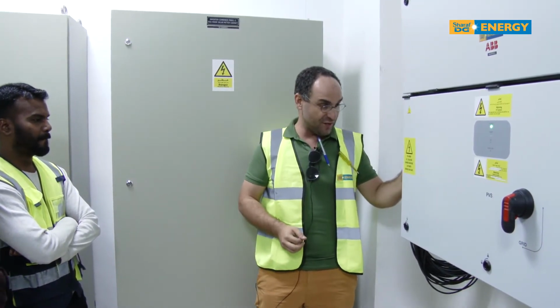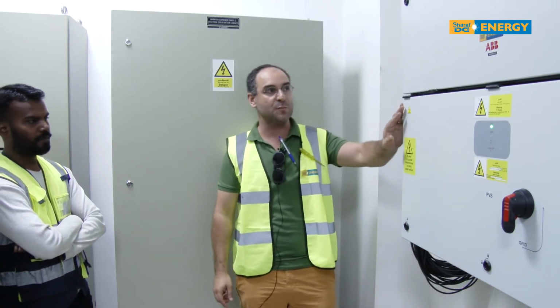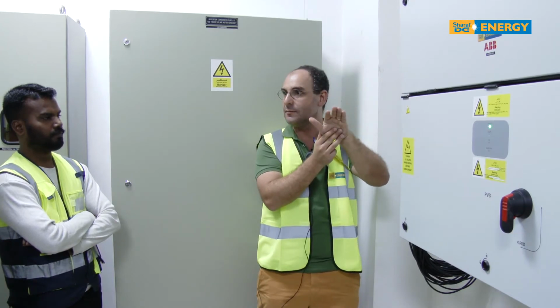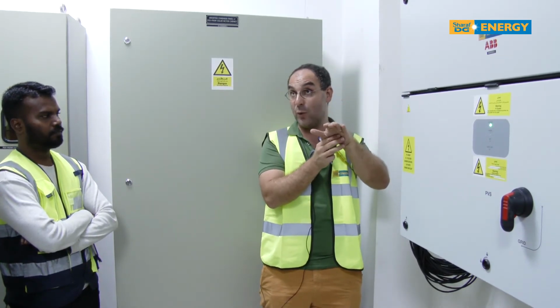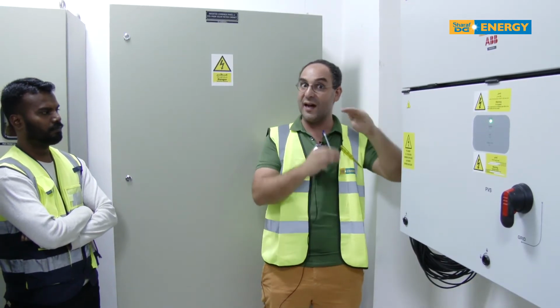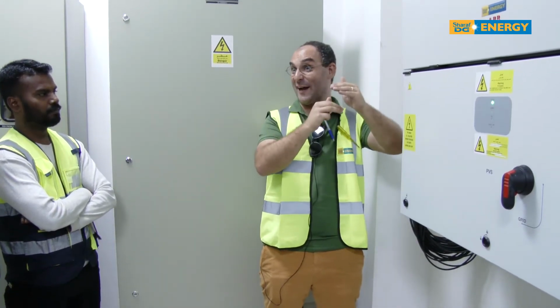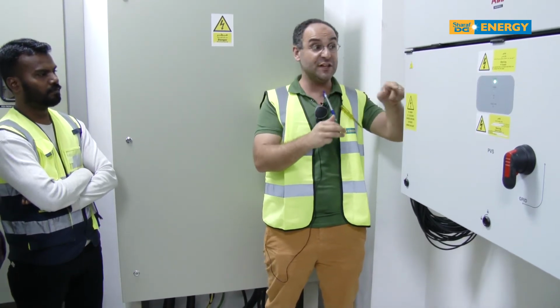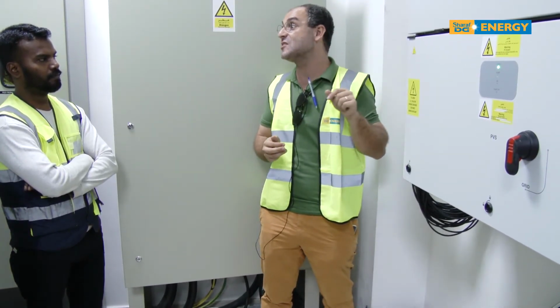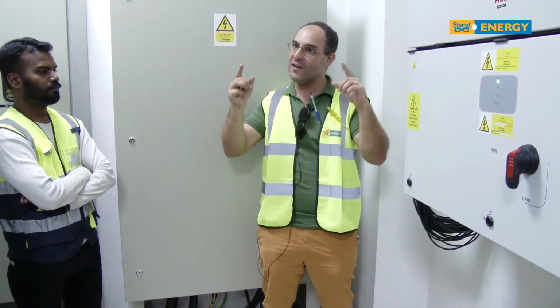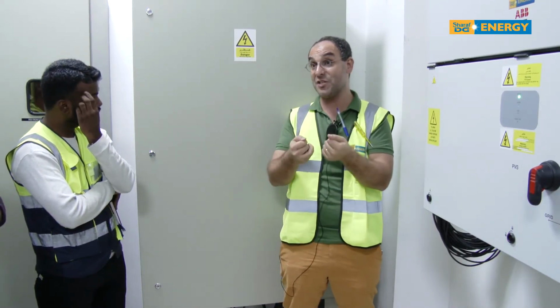All right? But GFI can be here, or it can be at that side. So what the inverter does, since it starts working this morning, is this: when the voltage built up in the channels is enough for the inverter to start, the inverter will do an insulation resistance test. Imagine you have a pipe from point A to point B, and you want to find a micro leakage on the pipe, sometimes not visible to our eyes, so you need to measure. So you put a lot of pressure inside that pipe to make sure there is no small leak. This is the same.